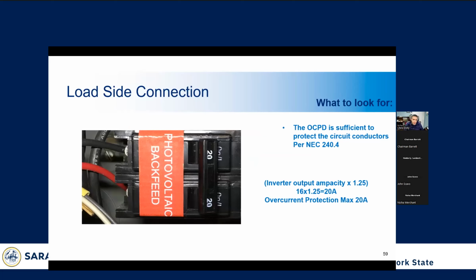As with all conductors of the system, the overcurrent protection has to be properly sized. Again, you want to size that at 25% higher than the rated output of the inverter. So you want to ensure that the wiring or the overcurrent protection is rated for 125% of the maximum output current of the inverter. Most backfeed breakers will be double breakers, which corresponds to what's in most homes. So you'll have equal distribution on each leg. Obviously, in more commercial applications, you might see differences.